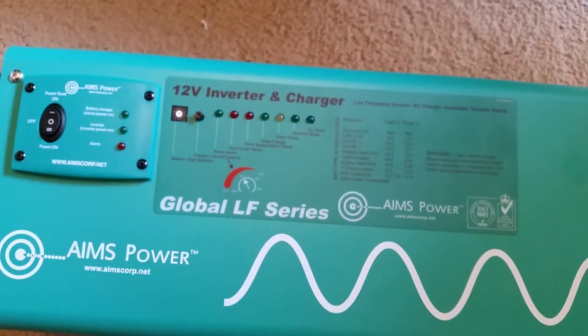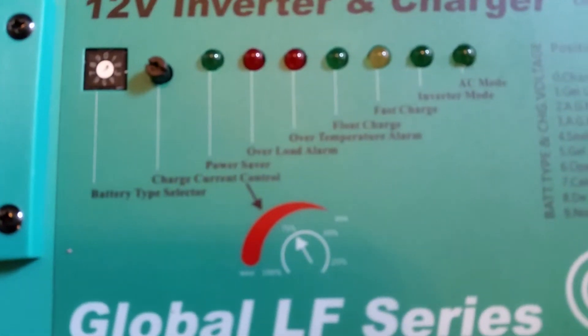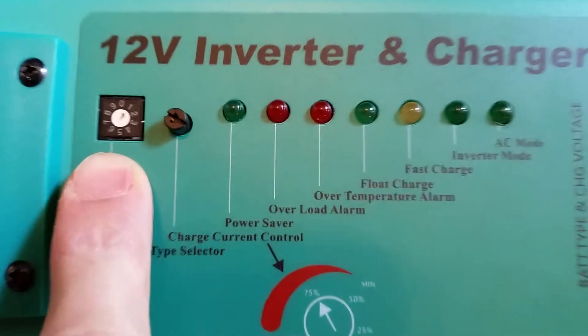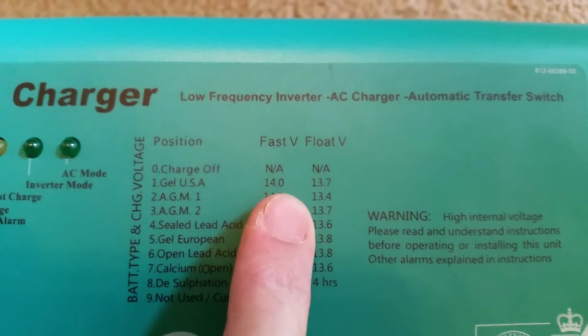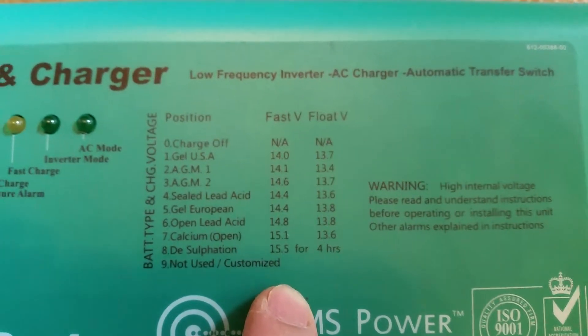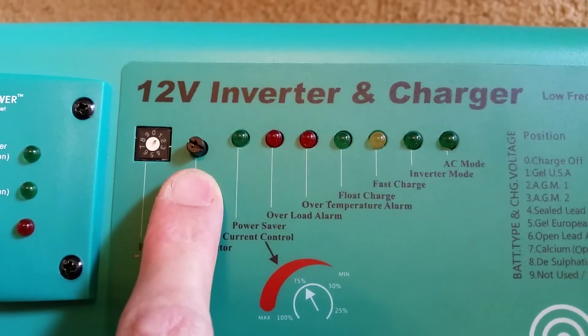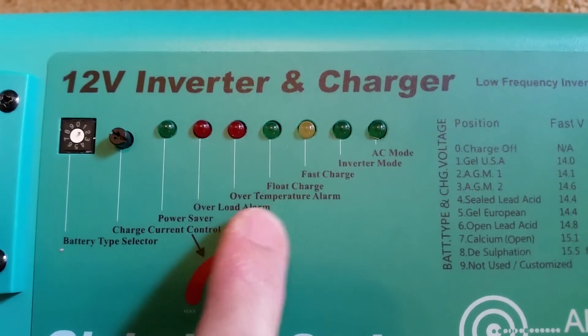That's an additional safety feature, though I'm still going to be putting AC breakers before and after this thing. I've always been curious what this diagram says — I've seen these on these inverters but never really looked at them closely. There's a battery type selector dial, and based on where you put that dial, this is the DC battery charging parameter it chooses for different kinds of batteries. I'm probably going to choose the AGM-1 version since it has the lowest float voltage, as this is just going to be floating the batteries the vast majority of the time.